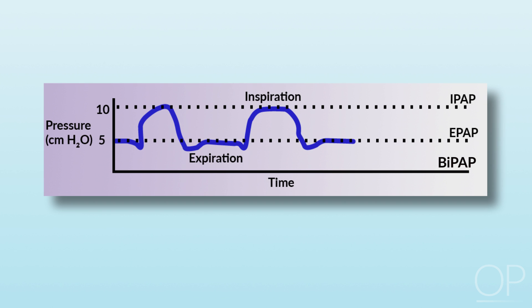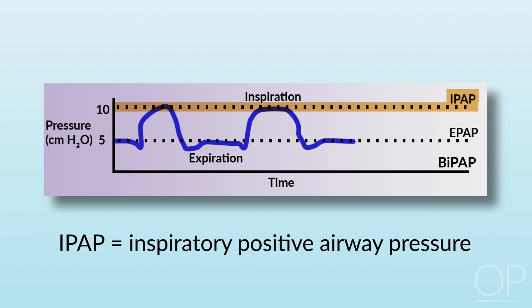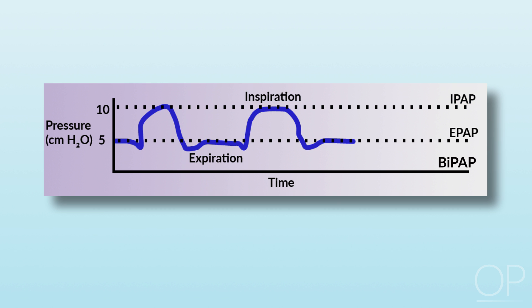The third graph shows a patient on BiPAP, where just like CPAP, there's a continuous positive airway pressure on the bottom, known as EPAP, or expiratory positive airway pressure, as well as an inspiratory positive airway pressure given to the patient when they draw a breath. It's an assisted breathing pattern, and pressures cycle between the expiratory positive airway pressure and the peak inspiratory positive airway pressure.